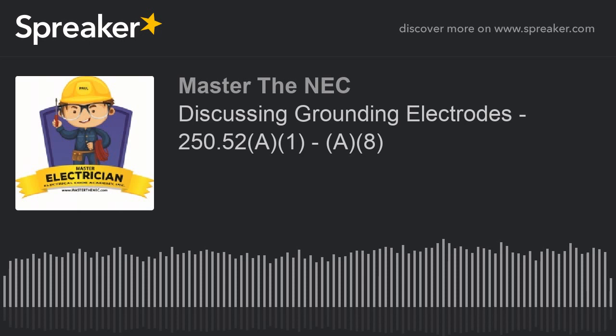So when I'm dealing with 250.50, I have now laid out the concept of having to tie or bond all of these electrodes together. Even if they're not present and I have to add one or more of them based on the rules in 250.50, I'm still going to tie them all together and I'm going to use them. If I add them, I have got to use them. In other words, I have to tie them together. Can I have more than one? Most certainly.